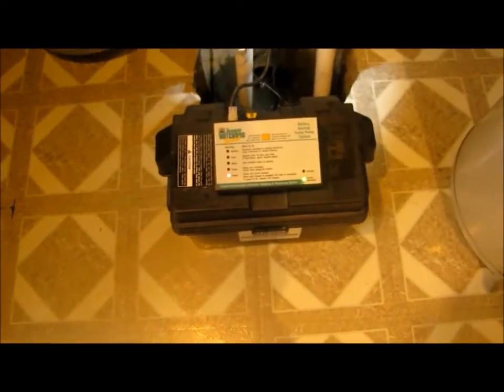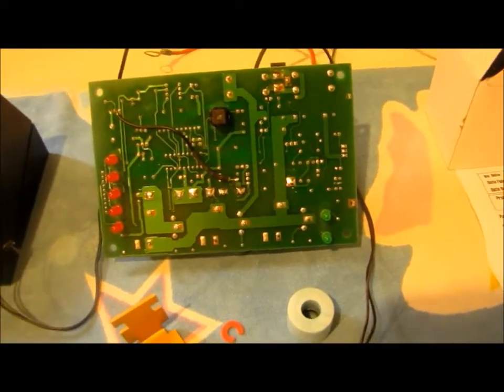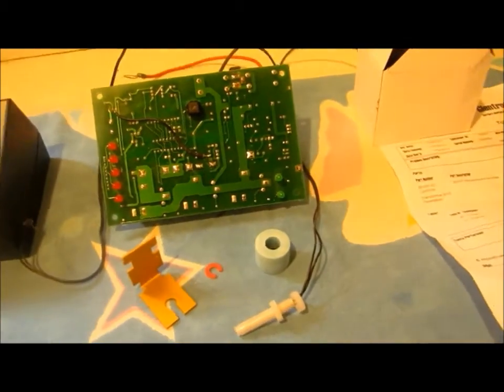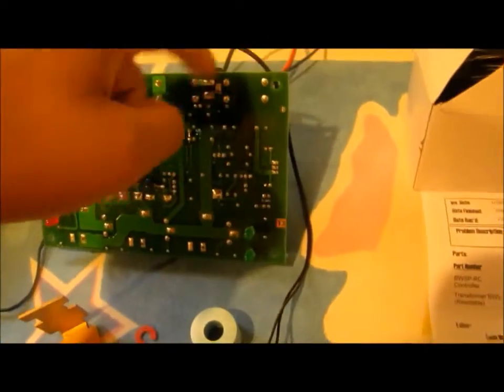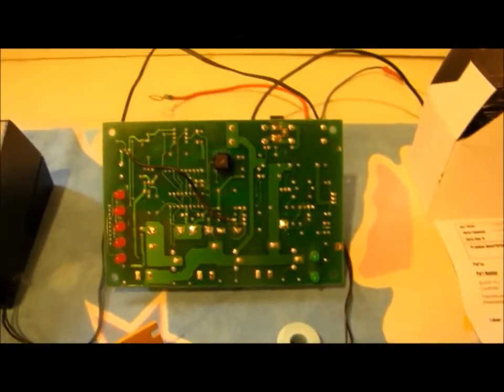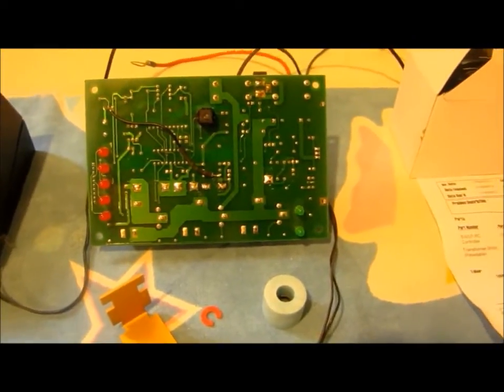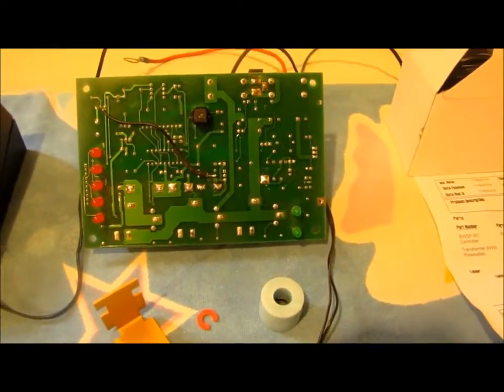The reason why I bought this brand new control unit is because this unit right here has a circuit board exposed. It had a problem with the battery alarm and the pump going off, as well as a charger problem. The battery alarm would go off every three weeks, and what they found out was it was a false alert from the system.